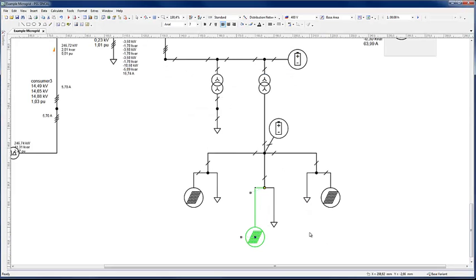The higher the number of similar consumers, the less likely they will be simultaneously active, and more loads of this type can be reduced. At any given node, only the number of similar consumers downstream are considered for the reduction factor.